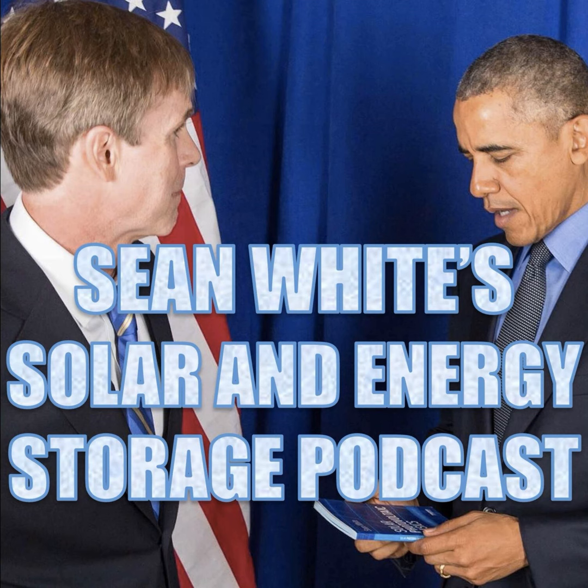You could have a 60 amp service. Houses, 1 and 2 family dwellings, are not permitted to have a service any smaller than 100 amps if it's a new service, but you have 60 amp services that are currently in existence today, and that's fully acceptable. And of course, those are going to have number 6 copper, probably, or 4 aluminum connected to them. Overcurrent protection with supply side connections, in a readily accessible location outside the building or inside the building. Overcurrent protection in dwellings needs to be within 10 feet from the point of connection. And other than residential dwellings inside, it needs to be within 16.5 feet of the connection point.